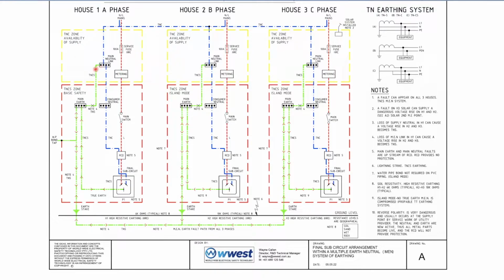The TNCS, which is for your basic safety, comes off where the earth, which is green, not like the blue of the neutral, goes down to your main earth. Then it goes from your main earth down to your earth stake, all the way down here to the ground. Then it goes over to your water pipe bond, your taps, your gas, whatever copper piping you've got in your house, and it's in what we call the TNCS zone, which is this red zone. It goes all the way around here, and this is called true earth. So it's the basic connection to outside true earth, through your water pipe, through your gas pipe, through your earth stake. They're the three connections that you've got, and that gives you the multiple earthing of the neutral.